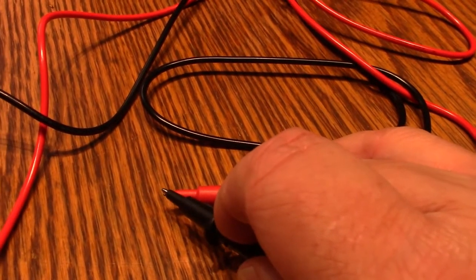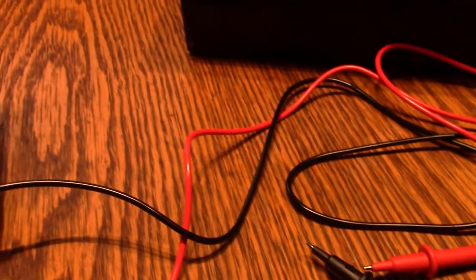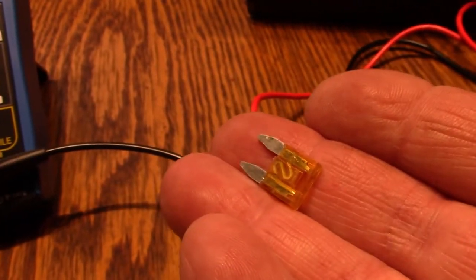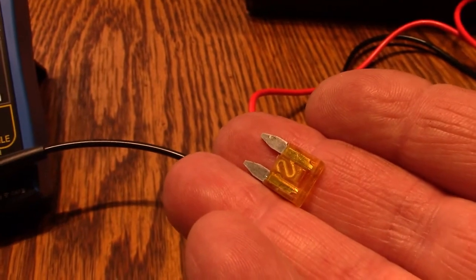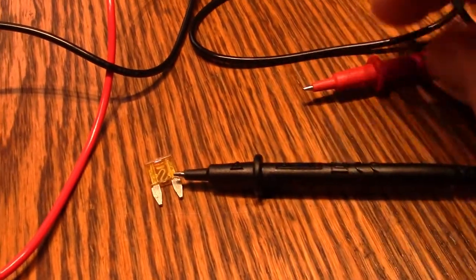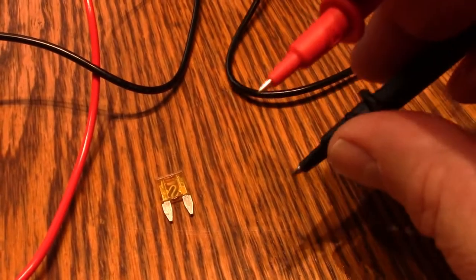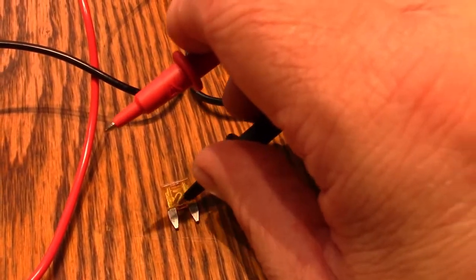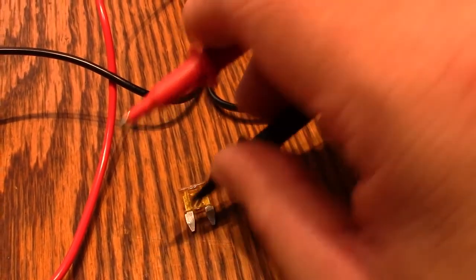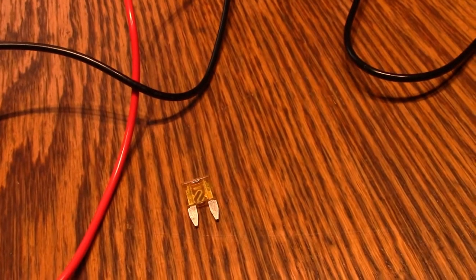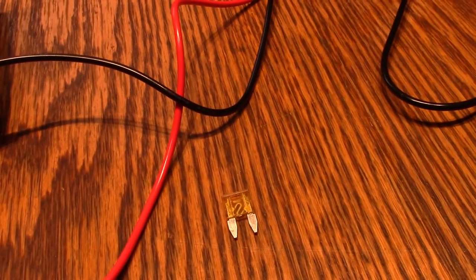If we can use that for testing, it allows us to see if fuses, for example, are still operational. If you look inside the fuse, you can see right there that there's a fusible link between the two contacts. And if we apply the meter probes from one side to the other, you'll see that we will indeed get a buzzing sound because continuity is going to run through. We're going to send current through one side of the fuse and then out the other. So this is an excellent tool then for checking your main fuse to ensure that it is still functional.